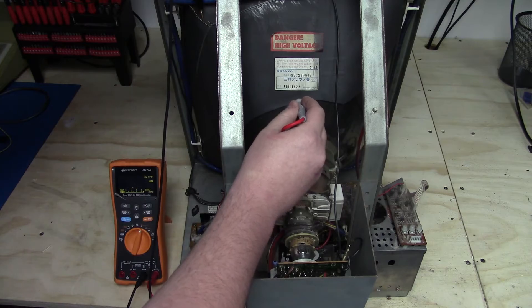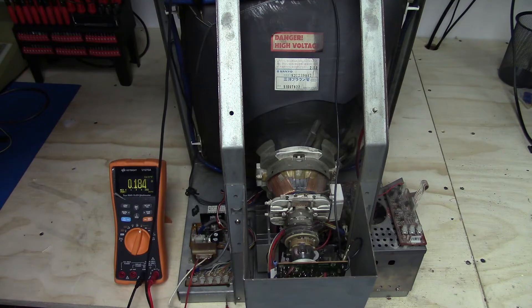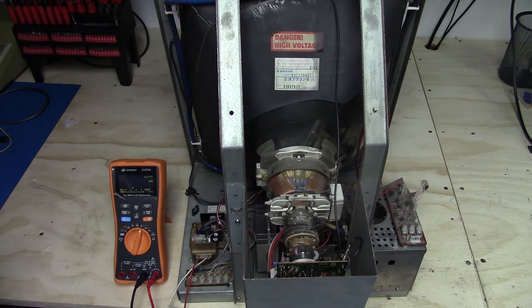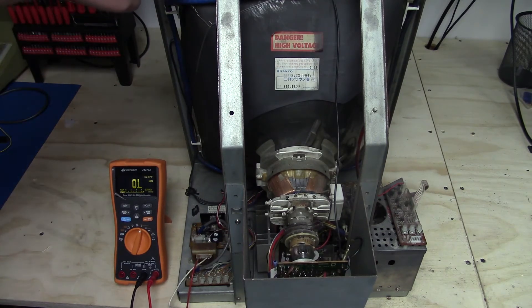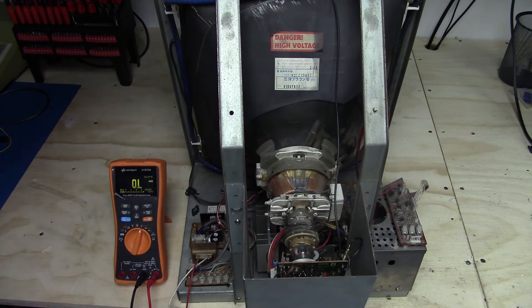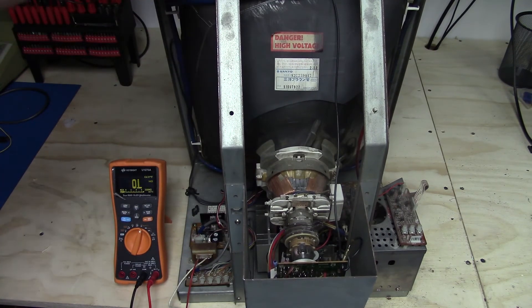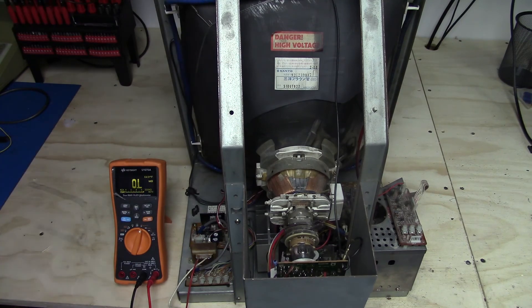So it's very important that this is connected. And of course, it does make its way back to the chassis itself. So if this is not grounded, the tube's not grounded. That means if you touch the tube, you're going to get shocked. So it's very important that this is grounded and your chassis is grounded. And it's also very important that all metal surfaces in your cabinet are grounded and it has a ground wall plug. Thanks guys.